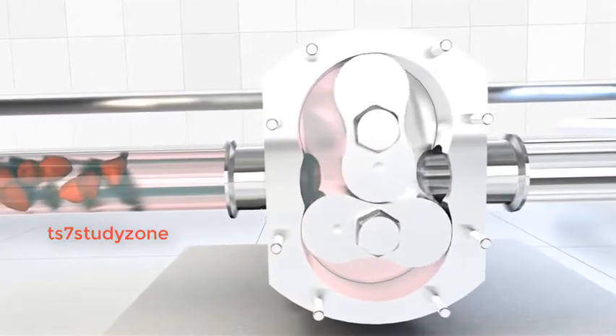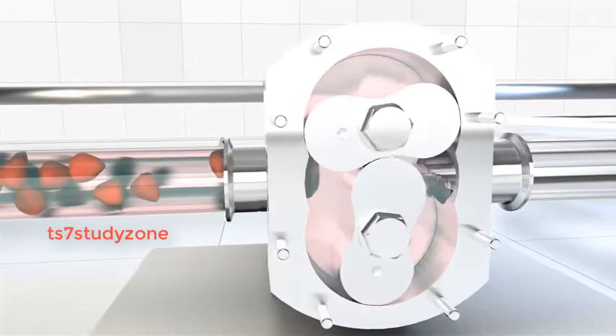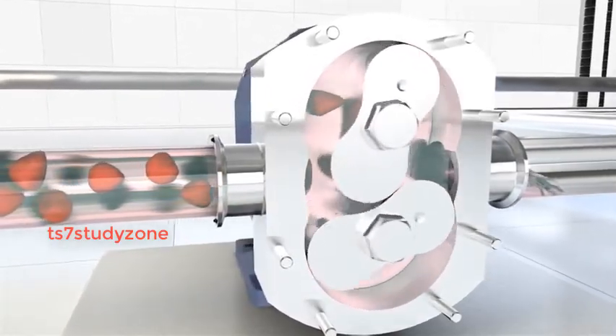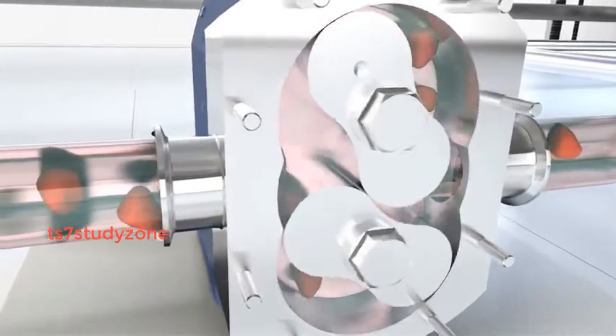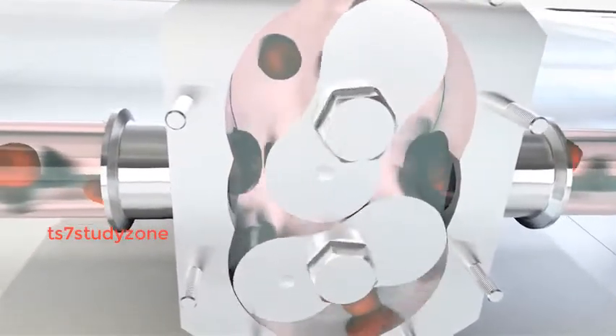The liquid travels around the interior of the casing in pockets between the lobes and the casing. It does not pass between the lobes. Finally, the meshing of the lobes forces liquid through the outlet port under high pressure.